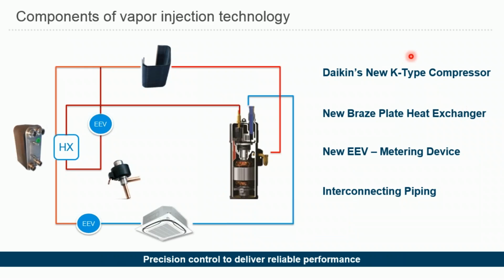Vapor injection. I'm not going to spend too much time on the vapor injection and how that happens, but the main components you will see in the vapor injection circuit are your new K-type compressor, obviously, which in addition to suction and discharge ports, gets this vapor injection hole. Outdoor unit coil, nothing changes there. On the indoor unit side, nothing changes there either. You're bringing in this new brazed plate heat exchanger and the new metering device, an additional EEV, to make that additional vapor injection happen. And you're sending this vapor back to your compressor through that additional injection port. That's basically how you make vapor injection happen throughout the operation.